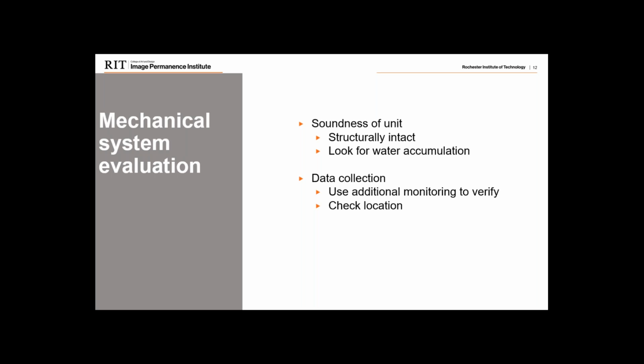What happens is you have what's called an adiabatic effect. That means that air that has already been dehumidified is passing over that standing water and will collect that moisture back up as it goes, bringing that moisture downstream. So you'll wind up having a higher humidity downstream than you'd like because of that standing water trapped in the unit. This is just two of many things, but really assess, as you're looking at the mechanical system, what does it look like? Are there any deficiencies we should be aware of? Are there any problems? And then also do some data collection, putting additional monitors within the air handling unit. We'll cover that in a few seconds.